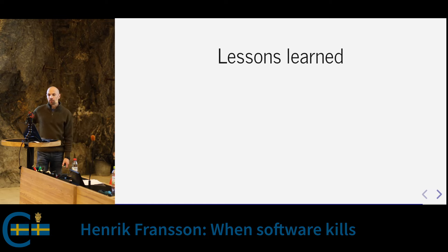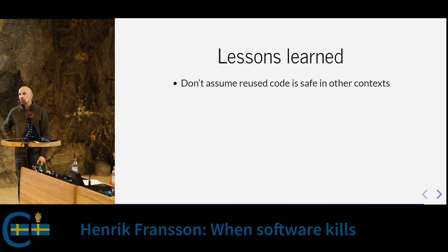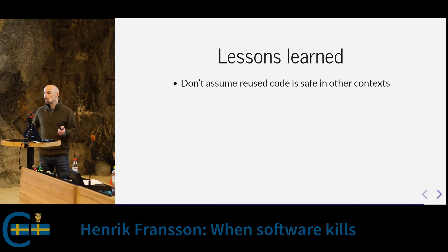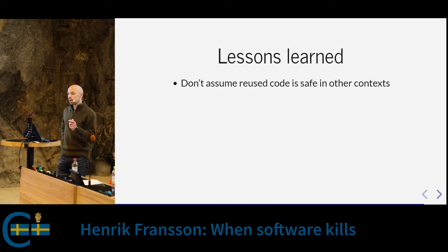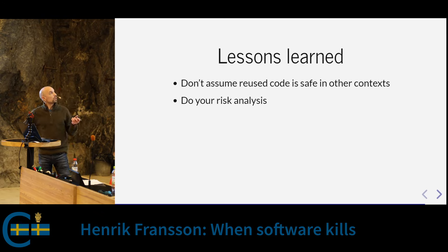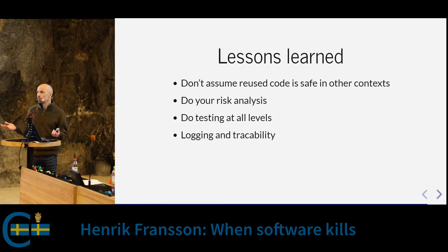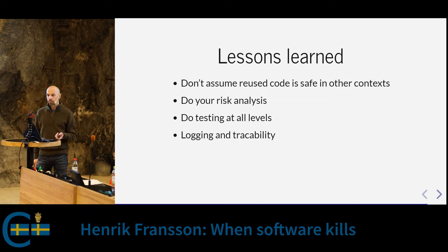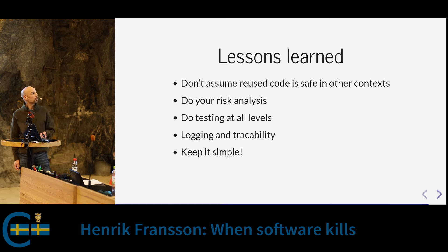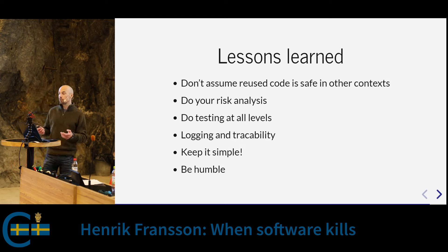Lessons learned: don't assume that just because you've used code for a long time it's correct or safe — doing the same thing over and over doesn't mean it's right when used in a different context or system. Do your risk analysis and testing. Make sure you have logging when things are in the field — when a person has died, you really need to know what went wrong. Keep your design simple; you remove a lot of bugs just by keeping things simple. And be humble — don't claim something is safe when you don't know that it is. You can actually never fully claim it is safe at all.